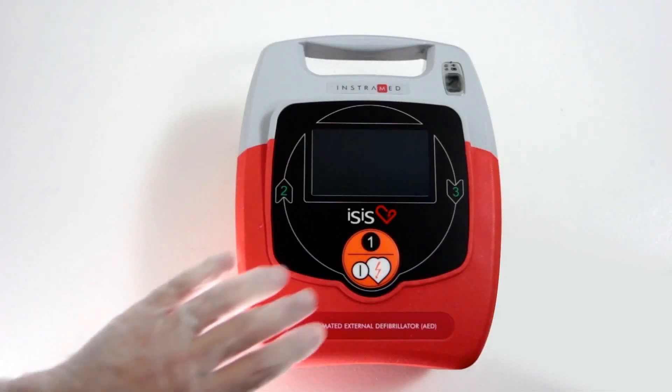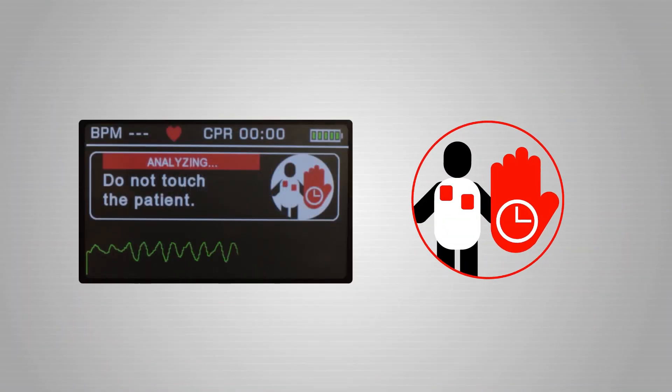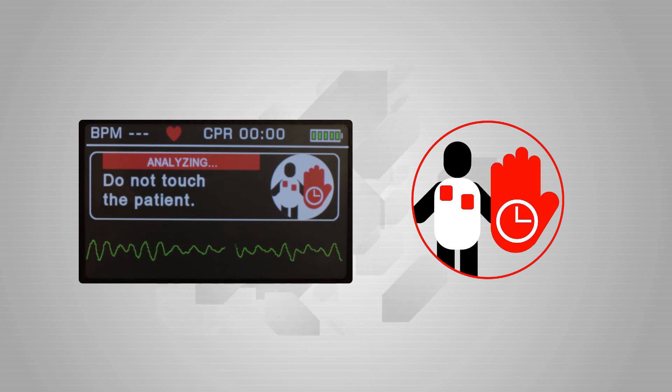Press the Start button. The ISIS will enter into its heart rate analysis mode and will initiate voice commands. Do not move or touch the patient, as this will interfere with the process of analysis.